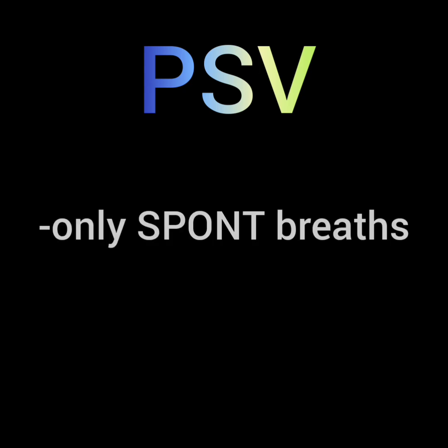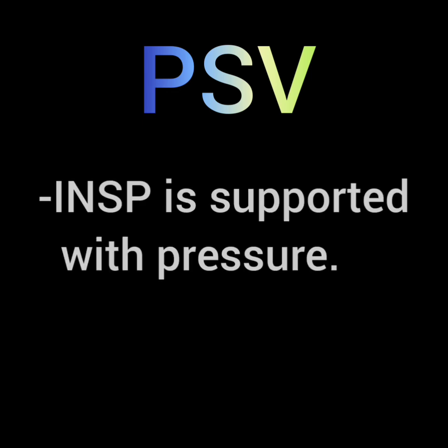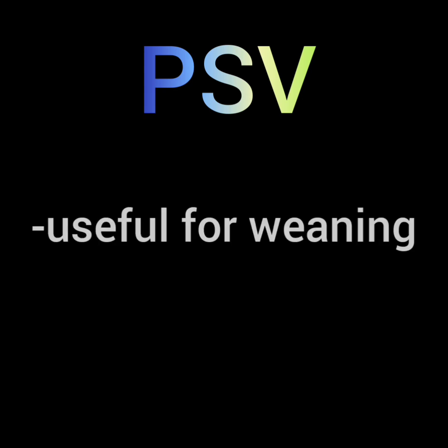One more mode most commonly used is pressure support ventilation. In pressure support ventilation, only spontaneous breaths are seen. There are no mandatory breaths, but these spontaneous breaths are supported by some pressure value. If you decrease this pressure value, then we can check whether the patient is capable of withstanding without ventilator support. So it is useful for weaning patients off the ventilator.